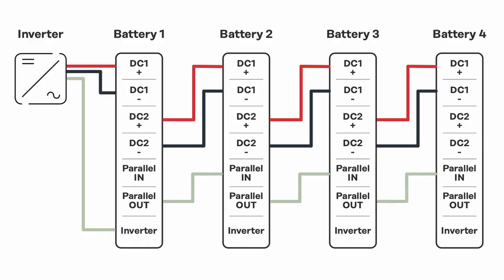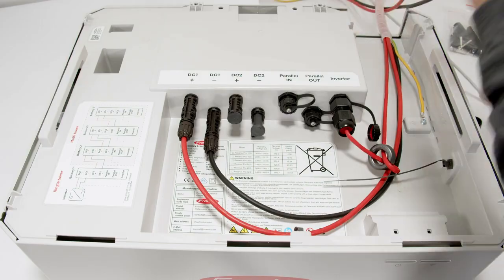At the last battery system, you're only taking the parallel in contact to connect the cable, and the parallel out contact stays open, so again there is no termination plug that goes into the parallel out contact.